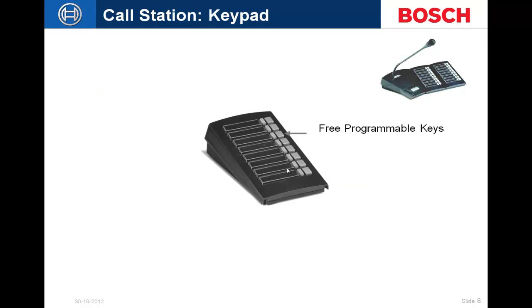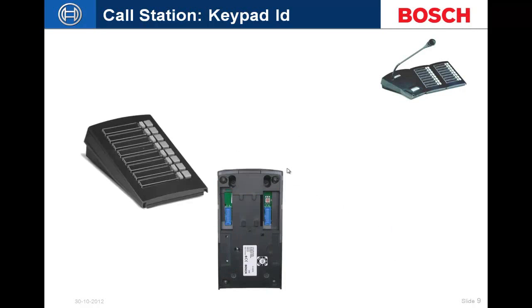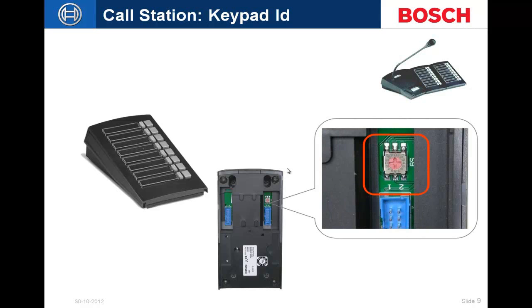Up to 16 keypads can be connected to the system. The keypads have removable key label covers — you can fill out an Excel spreadsheet with the keypad blanks, print and cut it out, and slip it under the label covers. Each button has a status LED. Key covers are available as replacement light pipes — remove the existing light pipe and press the new one into place. The keypads are addressable units with a hex dial on the rear, addressable from 0 through 15, and connected to the call station via ribbon cable.